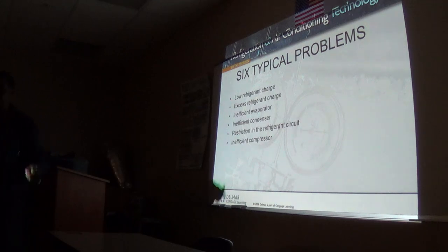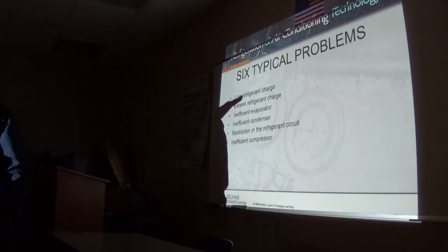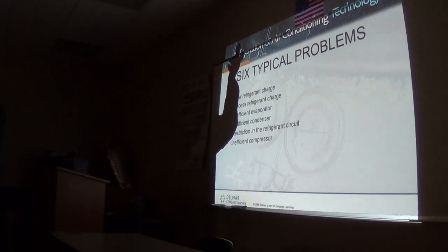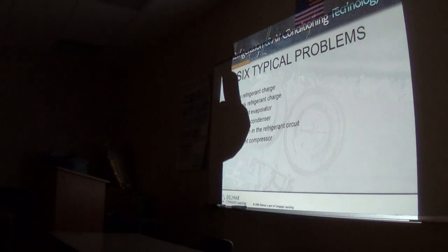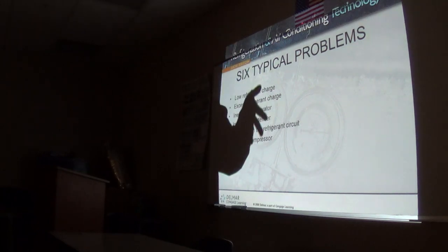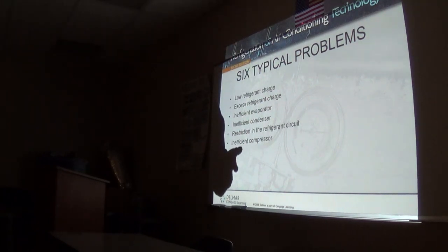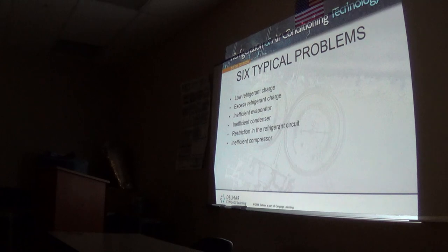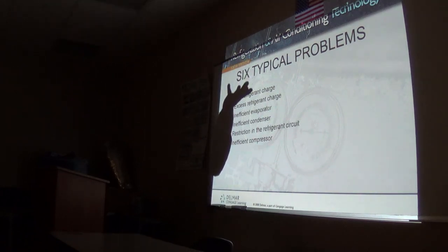And if the pressures equalize at that point, it has to be the compressor. It's not going to be the TXV. If you suspect it is the TXV, then you need to put some kind of valve in the line. You have to take that out. But I'll tell you how you can tell it's not the TXV. Guess what? The TXV is designed to do what?